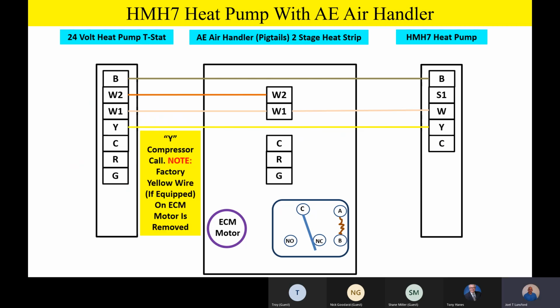Y terminal goes out to the compressor. That's our Y signal from the thermostat to the compressor. Now, please note something. Even though the HMH7 is a modulating unit, it'll modulate from 35 to 100% capacity, it's so simple to hook up. That's one of the reasons I really like this thing. All you have to have is a single Y terminal outside. We don't have a Y1, we don't have a Y2. It's just a single Y terminal going outside.